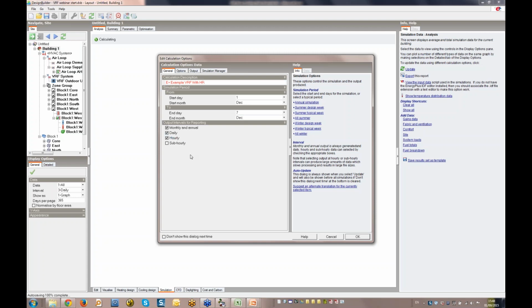I'm simulating the winter design week because, depending on the loads in your building zones, you may see no heat recovery unless you have reasonable heating and cooling loads. In this case, the core zone has high internal gains, so will need cooling, whereas the perimeter zones will require heating, so we should see a good effect.